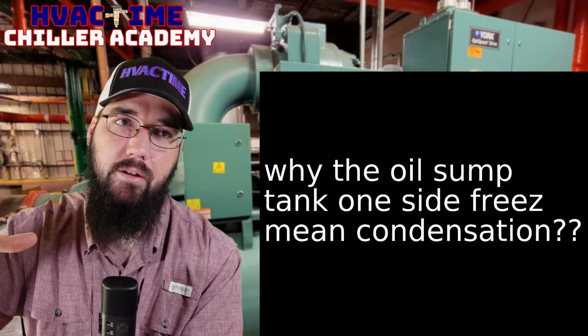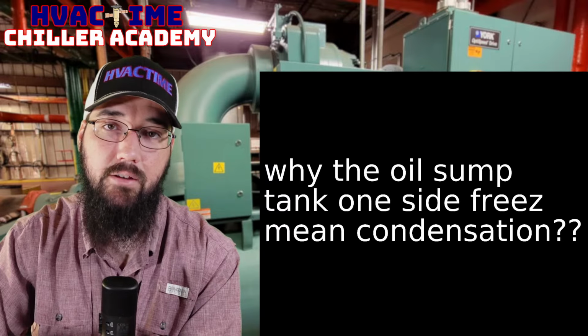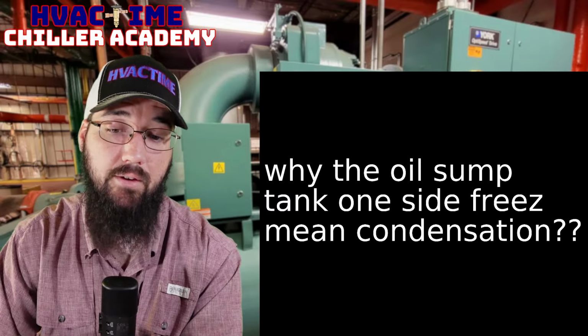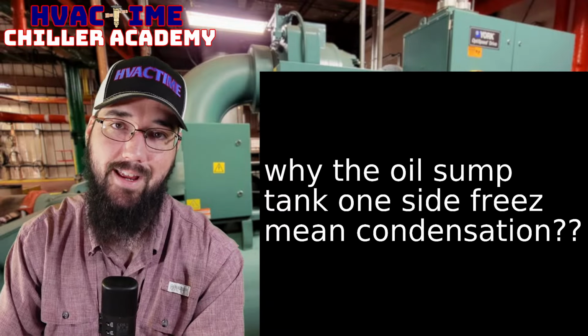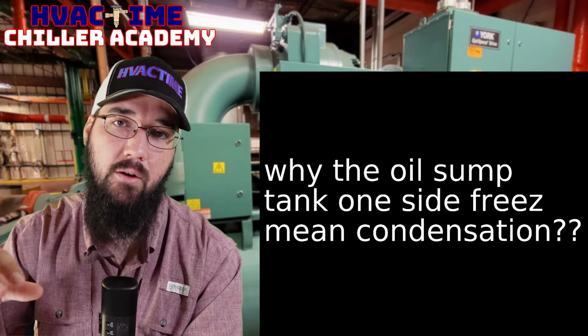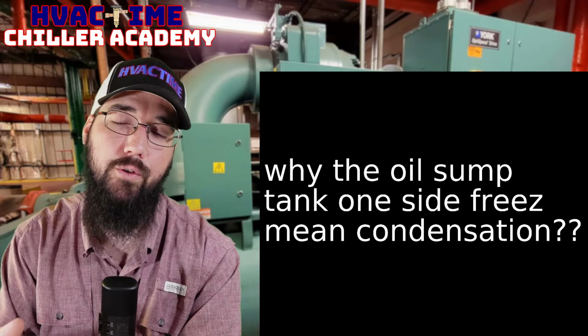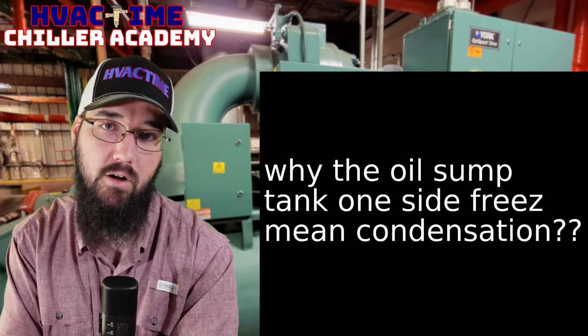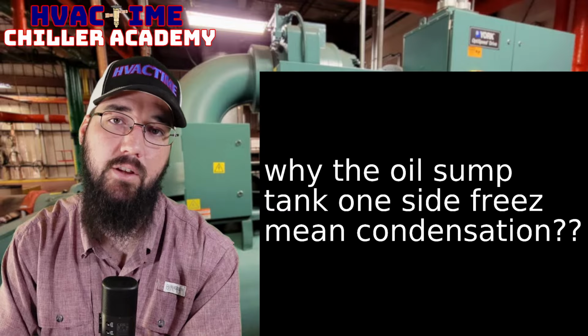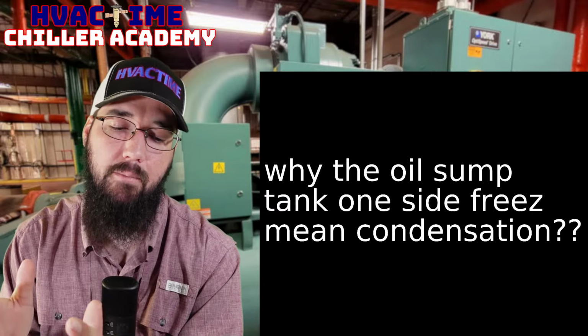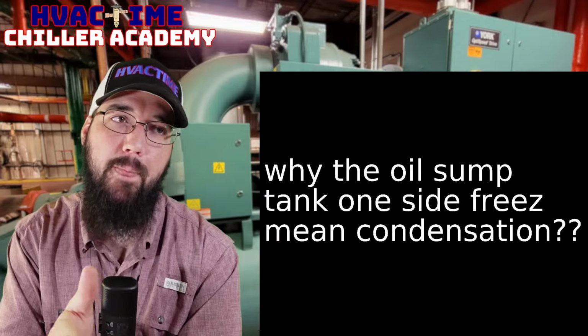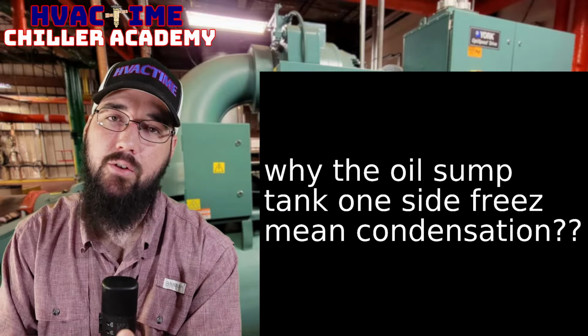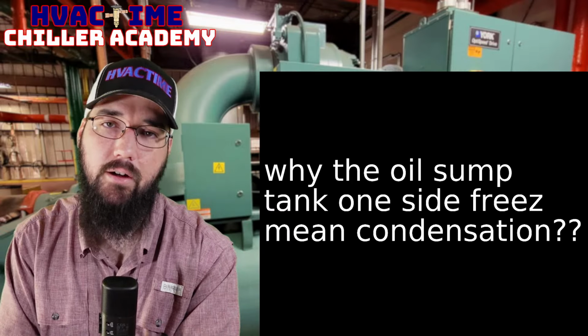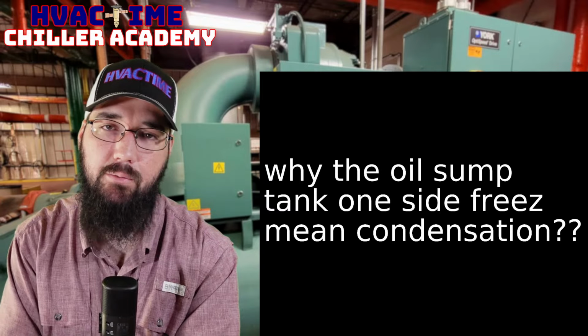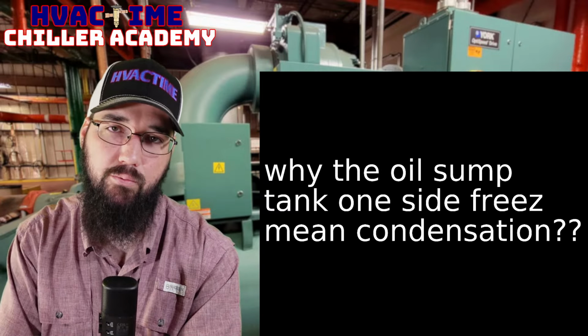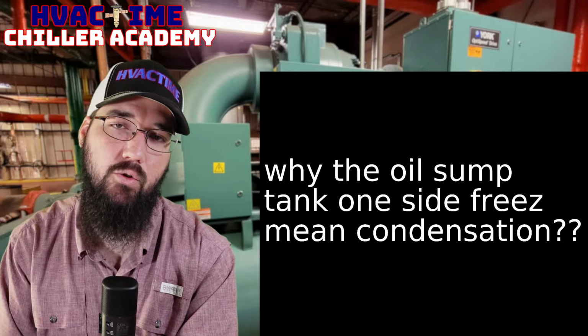ends up resulting in lower oil temperatures. It may not get so low that it trips off. I've seen where the oil sump temp is actually maintaining, but the top of the sump where the oil is not making surface contact is cold and sweating, or literally having ice form on it because it's so cold, even though the oil temperature itself down below is technically maintaining temperature. It's really weird to see, but that is that symptom, right? So on the YK, we need to get our liquid level under control there, as an example. Or on those CVs, the Trane CV series, you need to go close that eductor line off a little bit and calibrate that oil return, which you can do with it running.